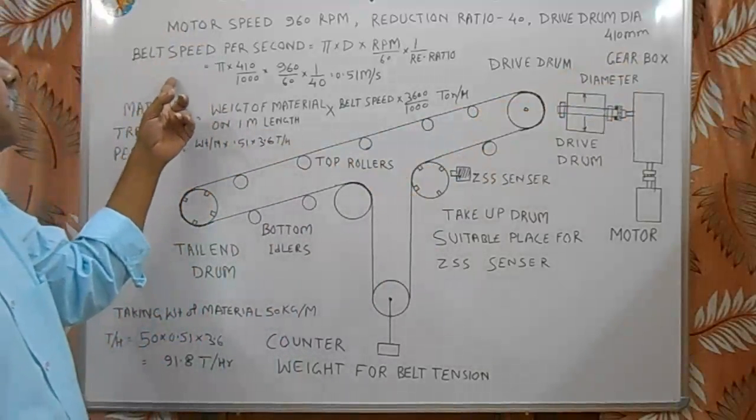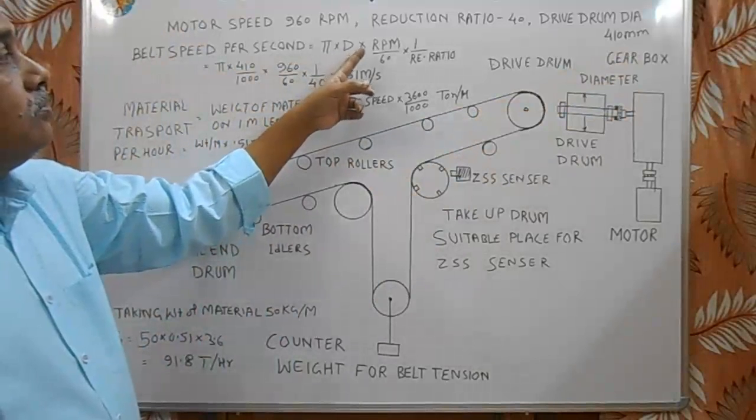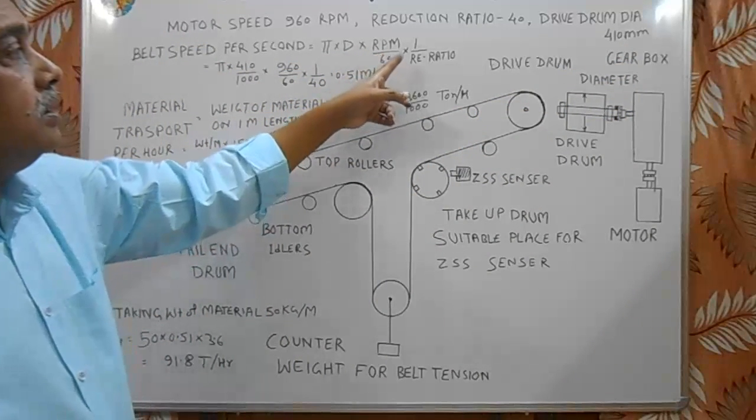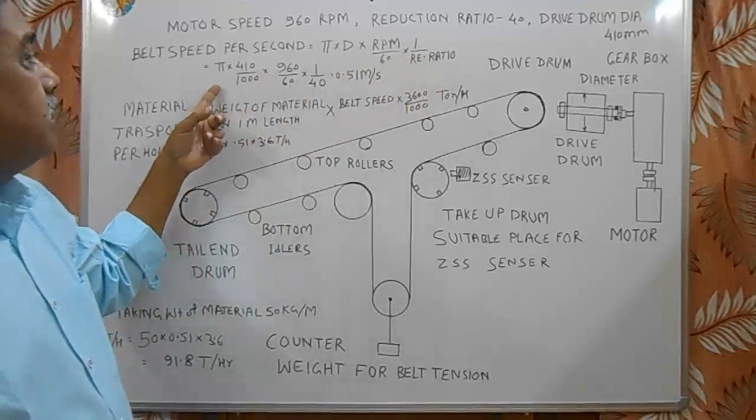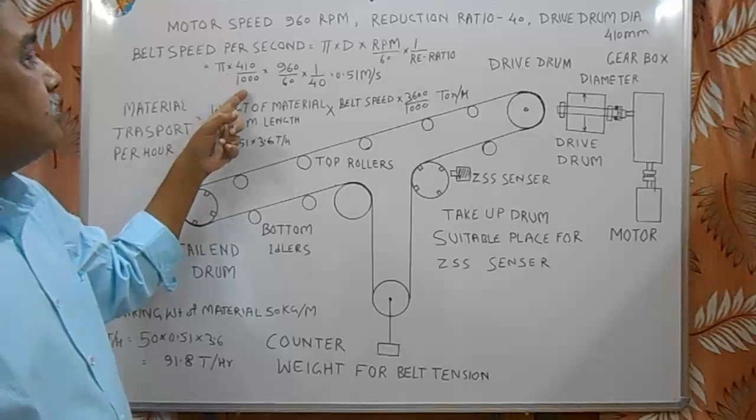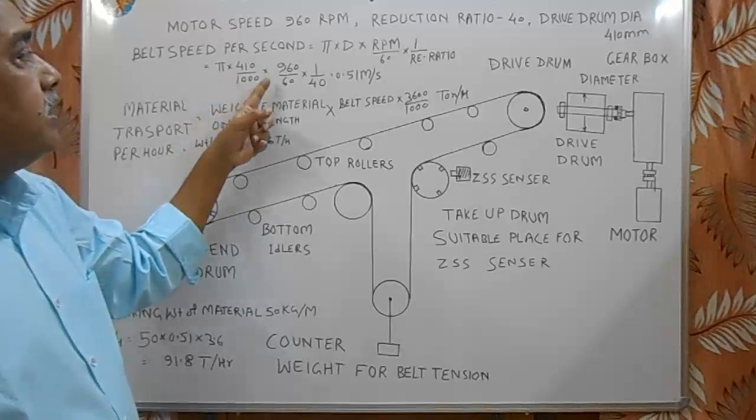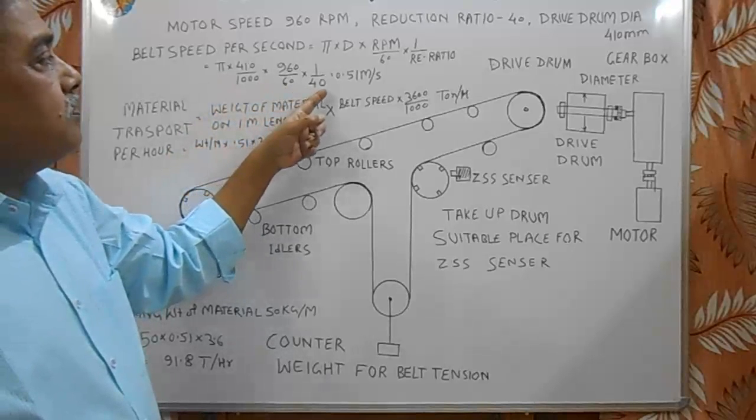So the belt speed per second is equal to pi into d into rpm of motor upon 60 into 1 by reduction ratio. That is equal to pi into drum diameter 410, 410 by 1000 to convert it in meters, multiply 960 by 60 speed in rps into 1 by 40 reduction ratio.